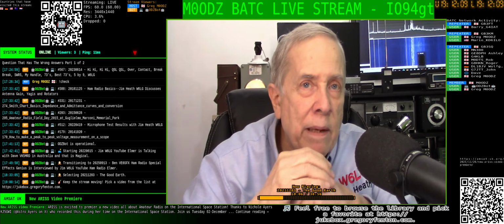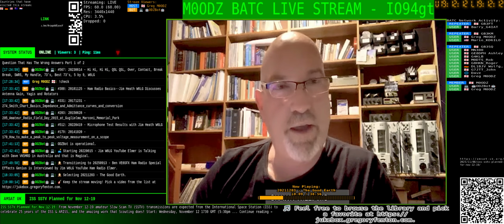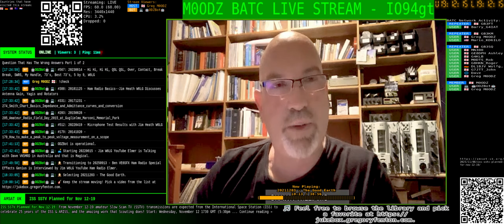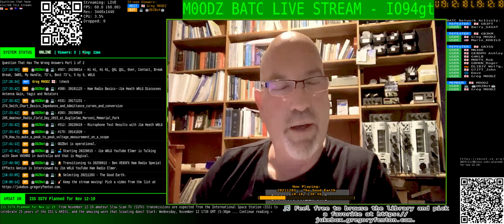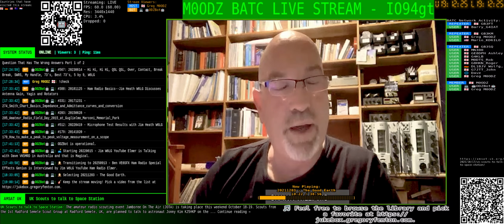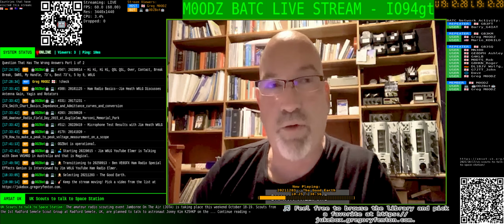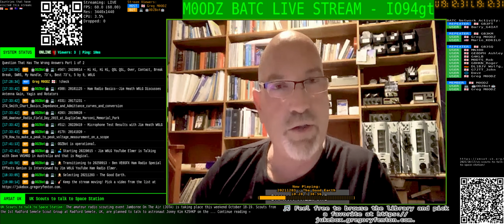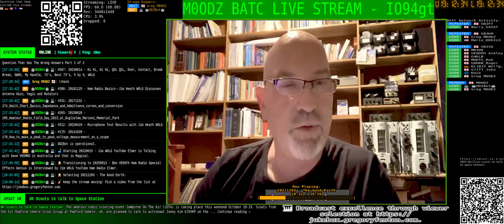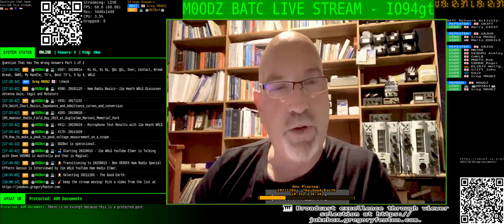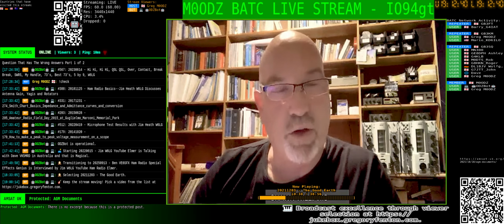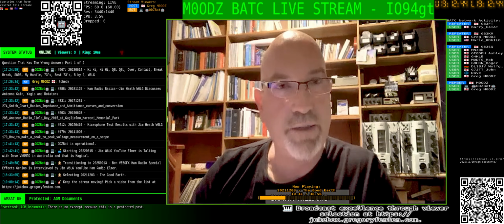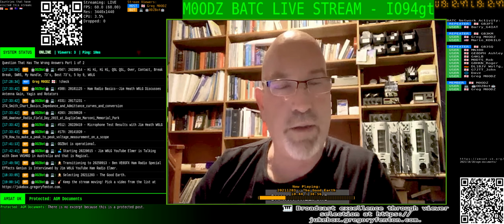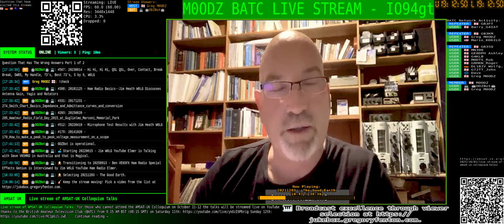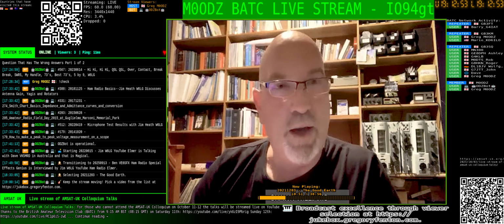And that's a contribution that came from what country? Yeah, that's a South African invention, and it's been a standard in South Africa for many years. And it saved a lot of lives. It's a good device to have. It can be annoying, and there are instances where you wouldn't use it. So, for instance, if you didn't want an earth leakage on your station, you could put an isolator close to your operating position, and you could bring in a circuit that's not on a residual earth leakage with an isolator within a meter and a half of your working position, and that would be legal. So there's a lot of ways to do it if you wanted to.